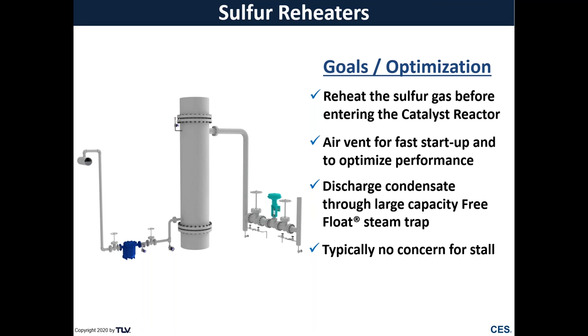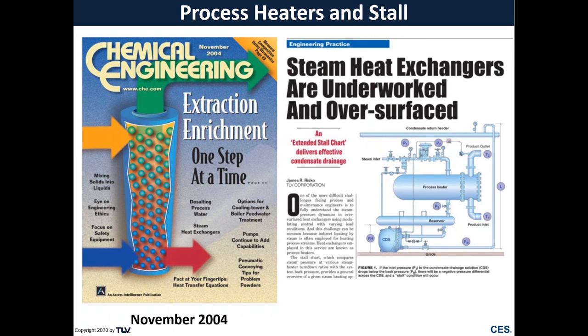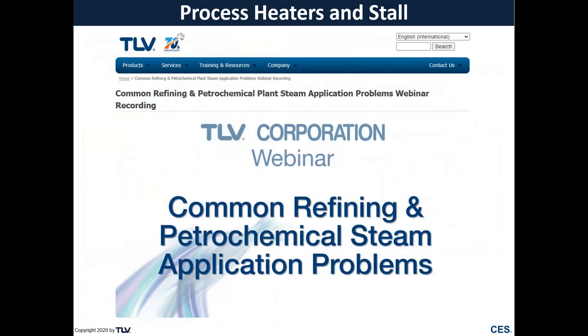Now, if you're asking yourself, well, what the heck is stall? Then I suggest that you read this article written by Mr. Jim Risko. And as I mentioned, stall should not normally be a problem within the SRU, but it is very, very common outside of the SRU, where typically lower process temperature requirements, modulating steam pressures, and oversurfaced heat exchangers combine to destroy heating performance and often make a nightmare of maintenance issues. You can also tune into part one of this series on common refining and petrochemical steam application problems, where process heaters and the concept of stall are discussed in great depth.